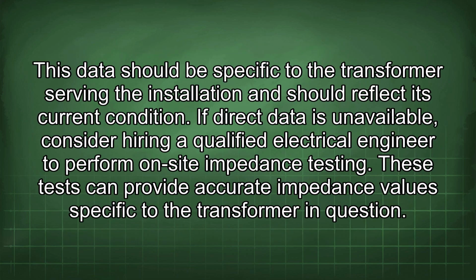This data should be specific to the transformer serving the installation and should reflect its current condition. If direct data is unavailable, consider hiring a qualified electrical engineer to perform on-site impedance testing. These tests can provide accurate impedance values specific to the transformer in question.